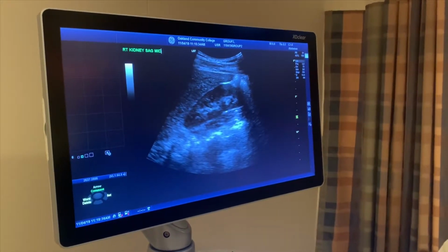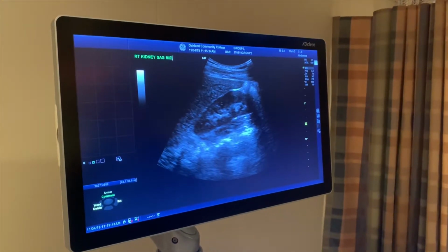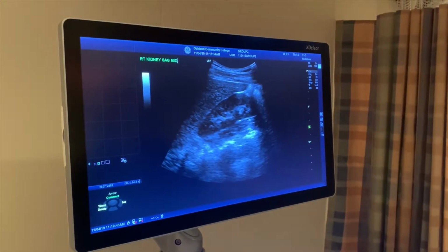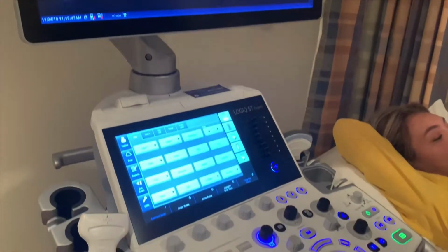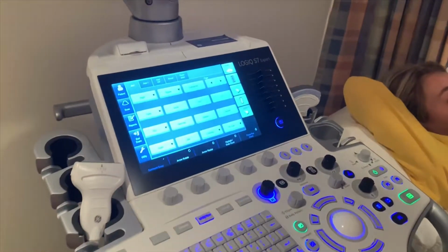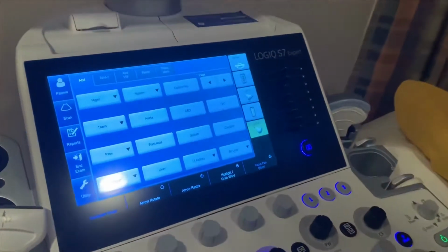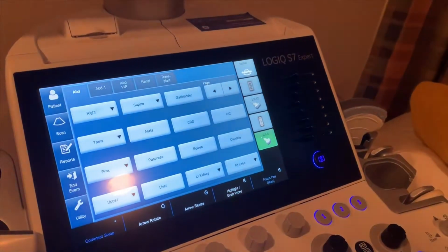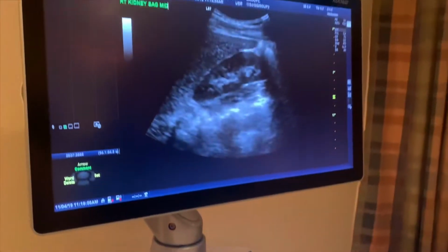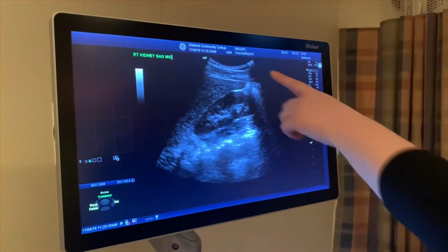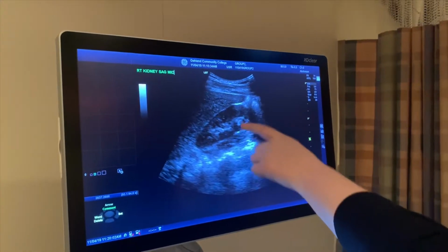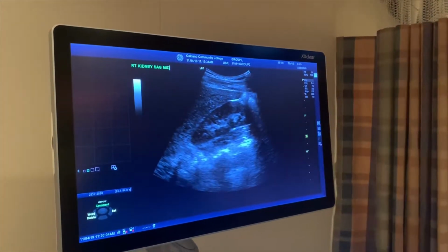As sonographers, we can also manipulate attenuation in a sense when we use our TGCs. Time gain compensation is called so because it compensates for attenuation of ultrasound energy with depth. Depth and time are somewhat synonymous in an ultrasound because the ultrasound machine calculates the depth of structures based on how long it takes for the ultrasound beam to reflect from the structure back to the transducer again.